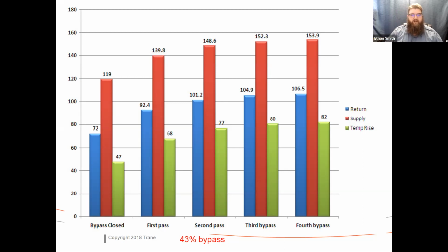Okay. There are some statistics out there that zoning systems with bypass dampers, even properly applied ones, will have anywhere from a 15 to 30% reduction in lifespan on the furnace. Okay, and that's with a properly adjusted bypass. So bypass has its place, but it's going to have some negative effects.